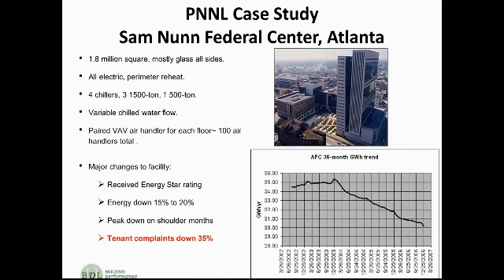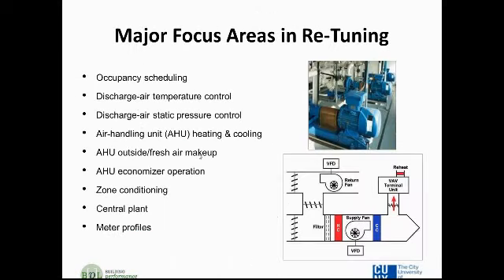So here is a PNNL, Pacific Northwest National Laboratory, case study. This is the Sam Nunn Federal Center in Atlanta, Georgia. It's a 1.8 million square foot facility. It has all electric perimeter reheat, 4 chillers, 3 of them 1,500 tons and 1 of them 500 tons, and variable chilled water flow. The VAV air handlers are paired for each floor, about 100 air handlers in total. As a result of this, I think this is about a 2-year effort, they received the Energy Star rating in the end.